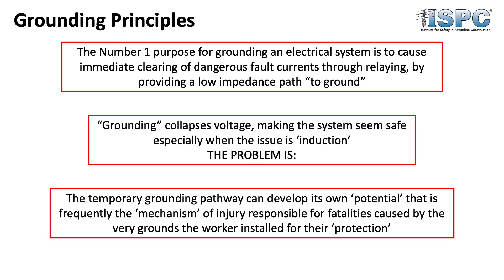When we apply grounding, it collapses the voltage, right? Makes the system seem safe, okay? Everything's good, we're grounded, right? Everything's intact, we're good. The problem is that temporary grounding that you just applied for your protection can develop its own potential. Okay? It can complete the path. You're still good at that point until you go to disconnect something. Okay? And then you break that path and you become that inserted resistance of that current carrying grounded conductor. Okay?